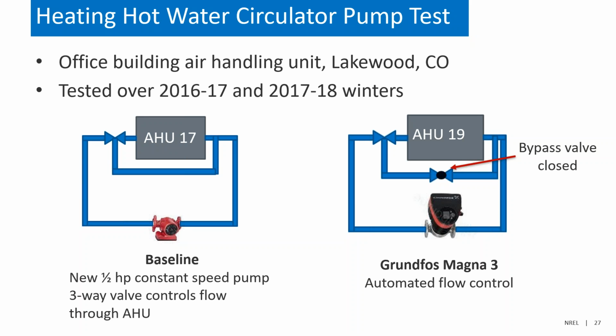So for the Magna 3, we essentially just installed a bypass valve, closed the 3-way, or converted this from a 3-way to 2-way valve, and then allowed for automated flow control with the pump itself.